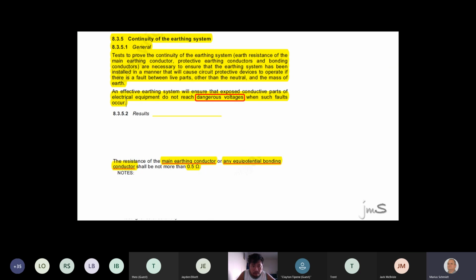So guys, just a matter of knowledge. You know what's the minimum size main earth conductor we're allowed to use? I'll give you a hint. Look at my 4 fingers. 4 mil. Is that right? What's the maximum measure you can get? 120. Right, in 3000, chapter 5, it tells you it can be between 4 mil and 120. Bonding conductor. What's the smallest you can go? Look at my 4 fingers. 4 mil. Right, 3000, 5.6 tells you that as well.